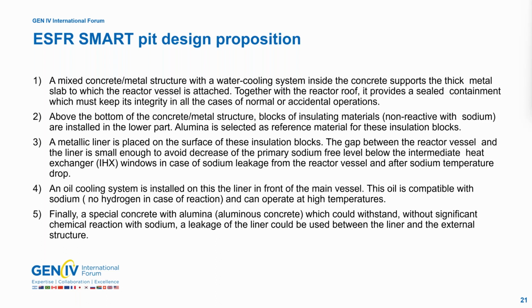A metallic liner is placed on the surface of these insulation blocks. The gap between the reactor vessel and the liner is small enough to avoid a decrease of the primary sodium free level in case of leakage. An oil cooling system is installed on the liner in front of the main vessel. This oil system is compatible with sodium. There is no hydrogen in case of reaction between oil and sodium, and this oil can operate at very high temperatures. Finally, a special aluminous concrete, which could withstand sodium without significant chemical reaction, could be used between the liner and the external structures. Next slide, please.